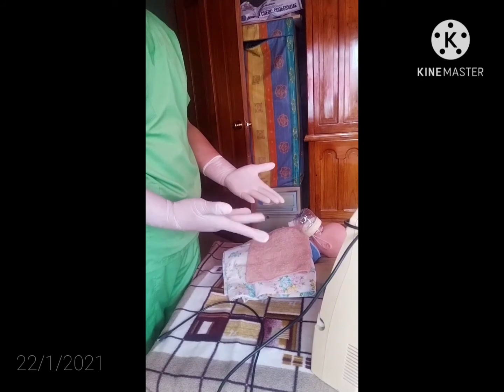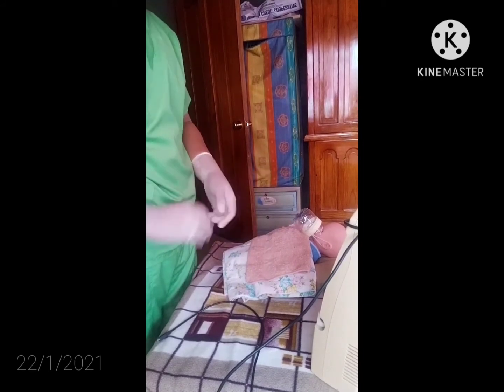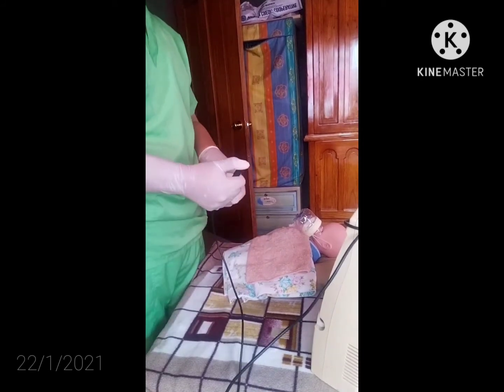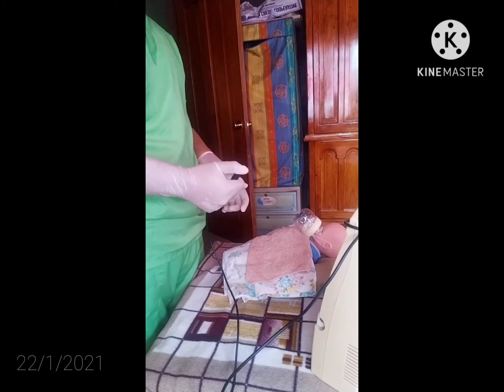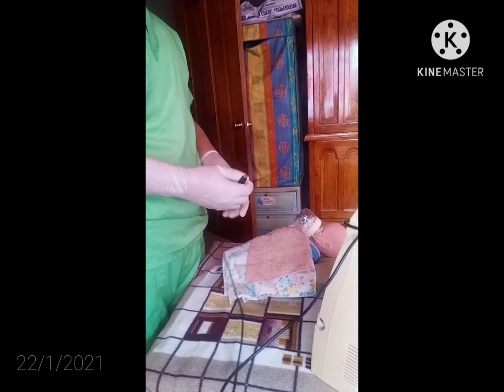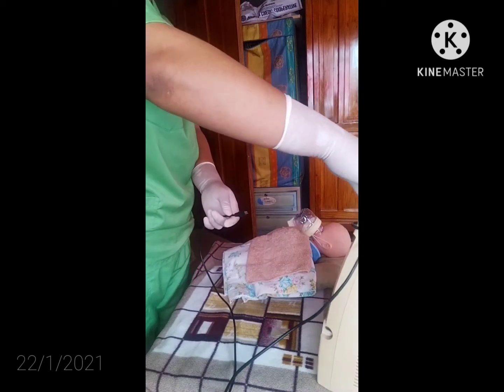Adjust the suction to the appropriate pressure, for our unit 60 to 80 mmHg. Put on disposable clean gloves and occlude the end of the connecting tubing to check the suction pressure. Place the connecting tubing in a convenient location.